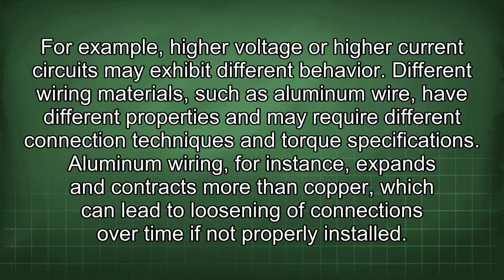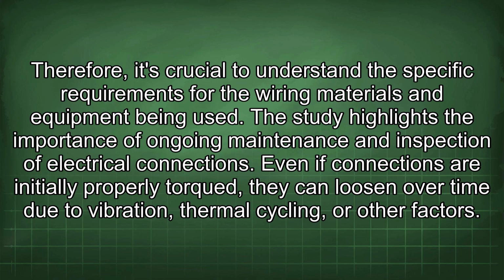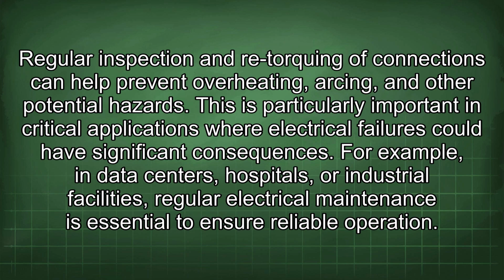Aluminum wiring, for instance, expands and contracts more than copper, which can lead to loosening of connections over time if not properly installed. Therefore, it's crucial to understand the specific requirements for the wiring materials and equipment being used. The study highlights the importance of ongoing maintenance and inspection of electrical connections. Even if connections are initially properly torqued, they can loosen over time due to vibration, thermal cycling, or other factors. Regular inspection and retorquing of connections can help prevent overheating, arcing, and other potential hazards.